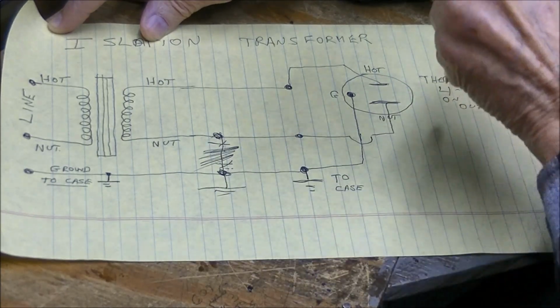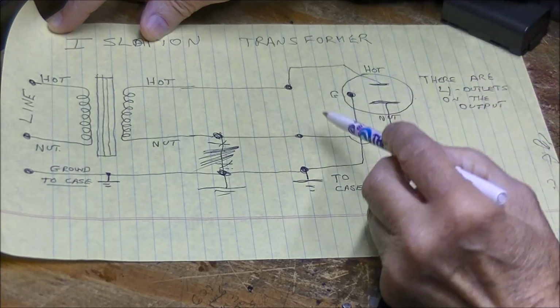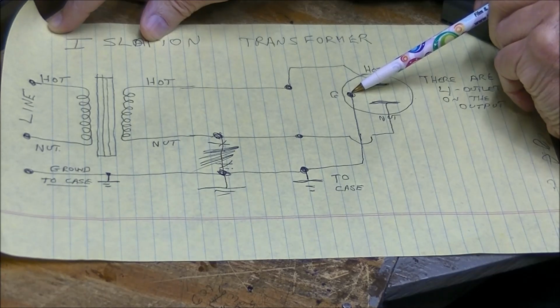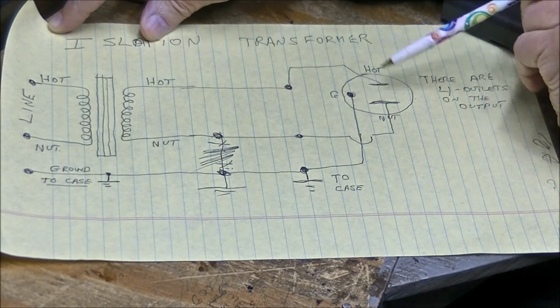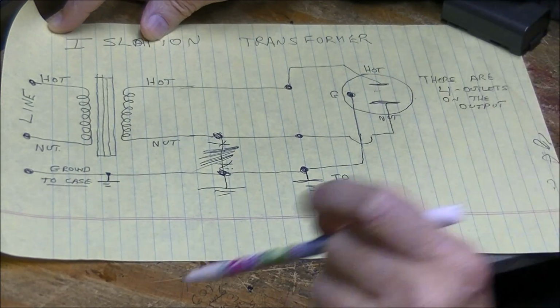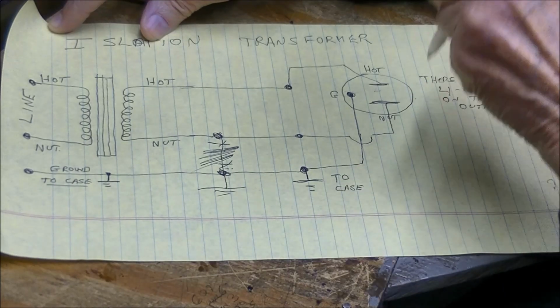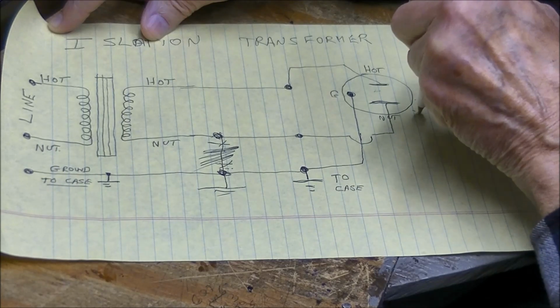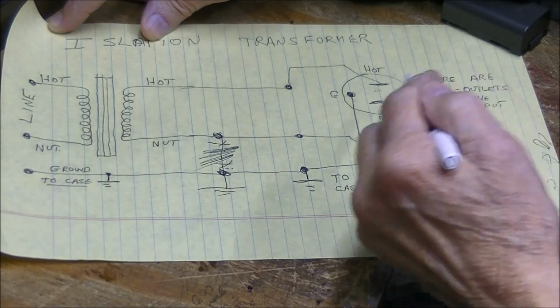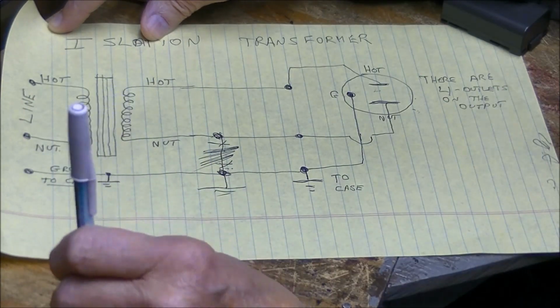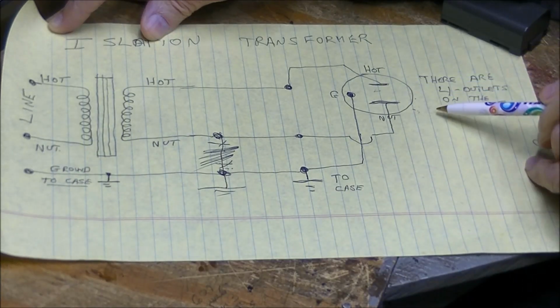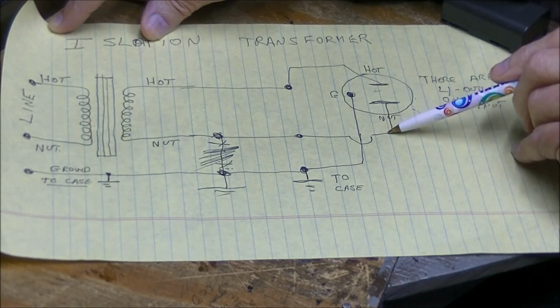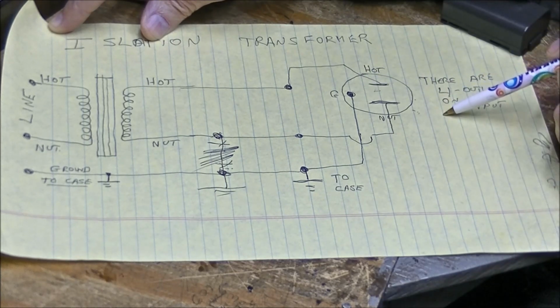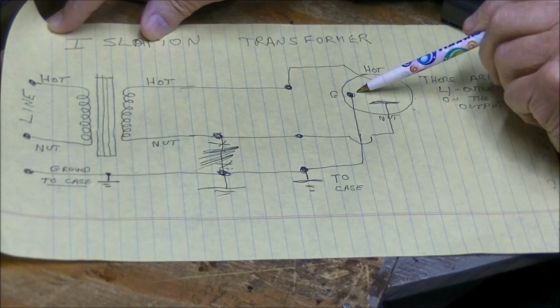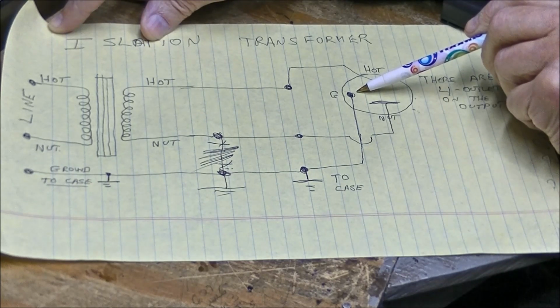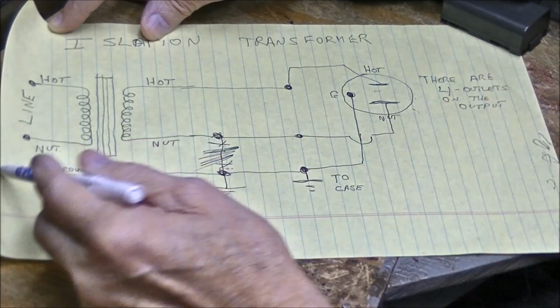So if you're using this on a device that has a third prong ground pin, and it's connected to the chassis, this is no longer an isolation transformer for a 3-prong radio, stereo, guitar amp, or anything else. There's no point in using this because it will not protect you, because you've got a complete circuit, should you come in contact with the hot wire and the case of the isolation transformer or the chassis of the device under test, because that device is using a 3-prong wire and grounds the chassis—what essentially is a complete circuit back to the circuit panel.